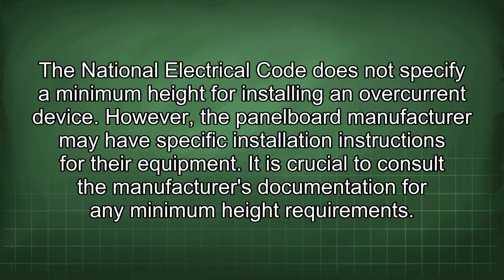The National Electrical Code does not specify a minimum height for installing an overcurrent device. However, the panelboard manufacturer may have specific installation instructions for their equipment. It is crucial to consult the manufacturer's documentation for any minimum height requirements.